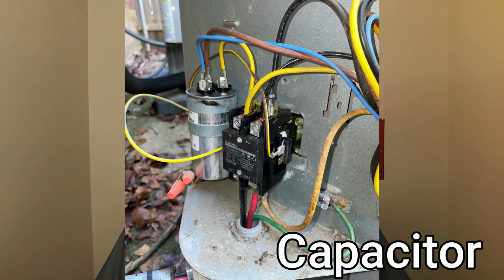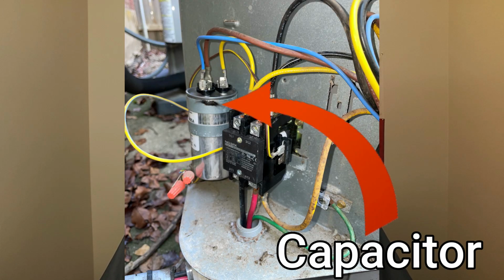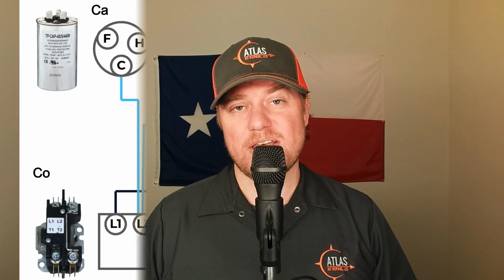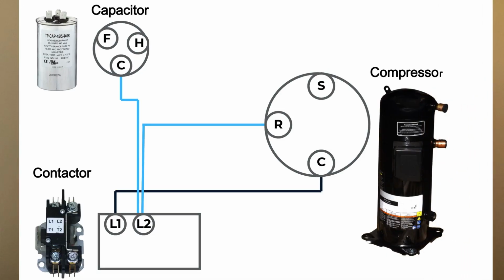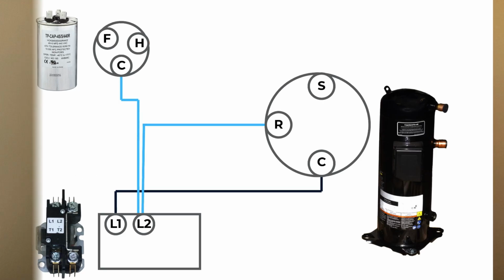A run capacitor is in use the entire time the AC is operating. So the way that a run capacitor works, not to get too technical, is as power is being fed through it, it is directing that power into 2 different locations, kind of like creating artificial 2-phase power. And this will feed things like the compressor. So as the capacitor weakens over time and is no longer operating within factory spec, the power that it's delivering begins to weaken to the point where it's not delivering the power correctly, aka where the artificial 2-phase power that it's creating is breaking down.